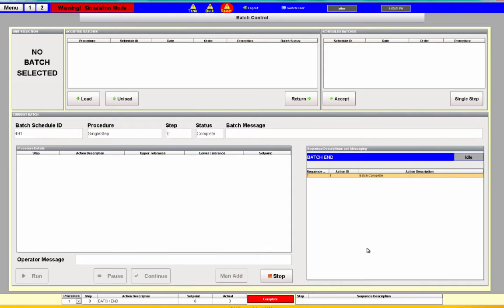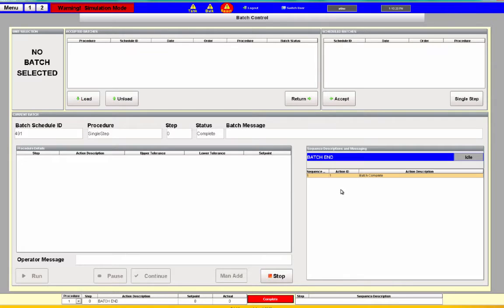Each batch procedure is made up of a group of sequences. When I say a sequence, I mean something like fill a tank. If you fill a tank with water, we'll have a sequence for that. If we want to fill 10 different tanks with water, that may be our procedure and we'll have 10 different steps. Each step will fill a different tank — it handles opening the valves, starting the pumps, and doing all that kind of stuff. Over here you'll see what sequence is running.